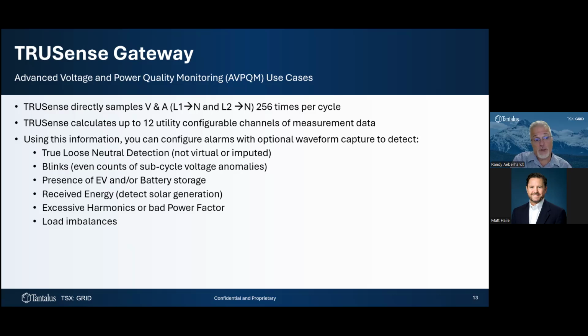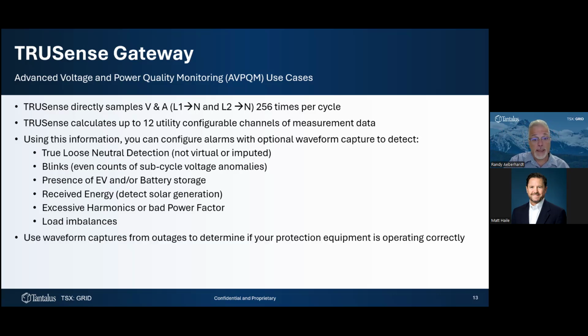You can get alarms on excessive harmonics or bad power factor. We can look for load imbalances, because we're measuring line one to neutral and line two to neutral separately. You can look to see if there's a real disparity between amperages on line one versus line two, and balance accordingly.